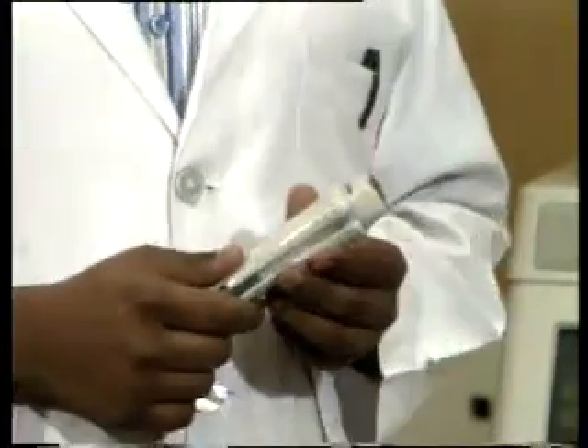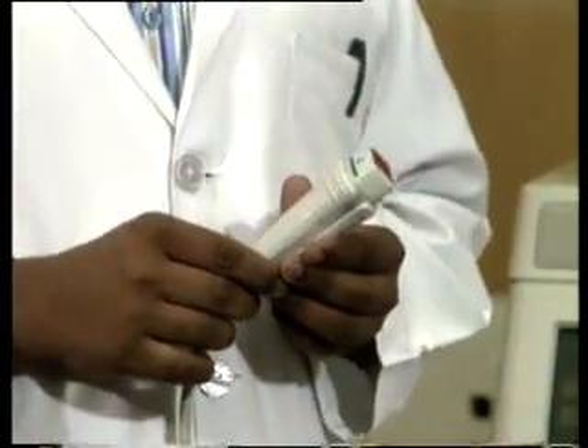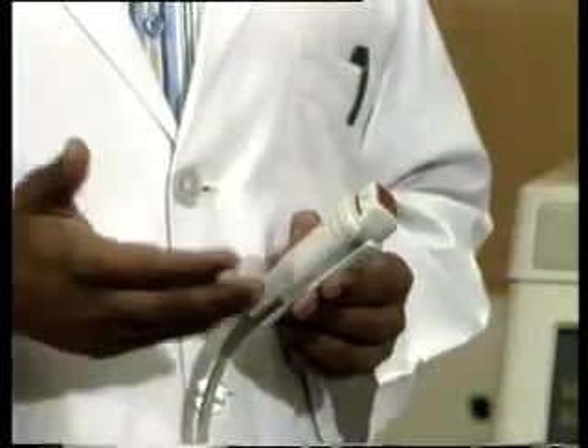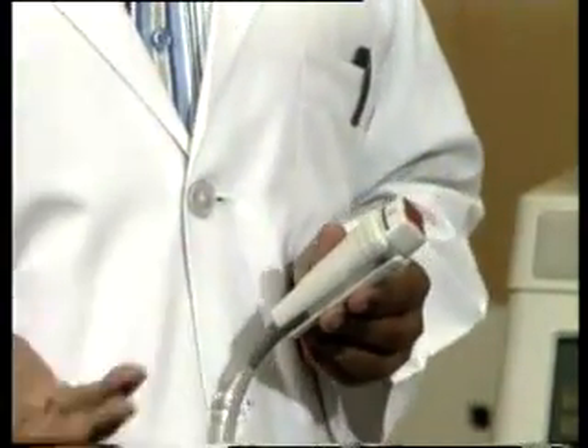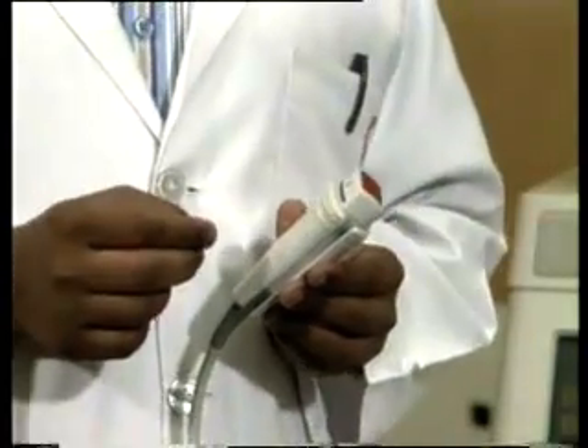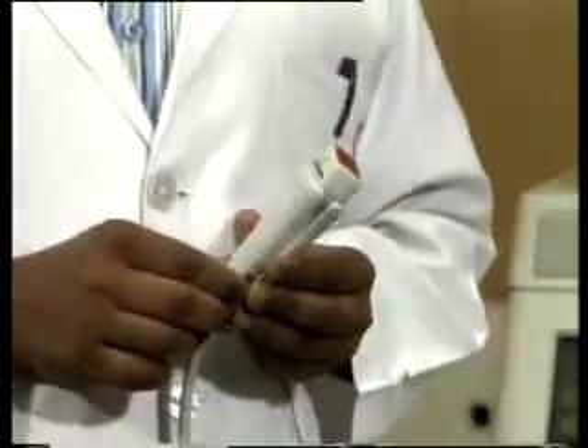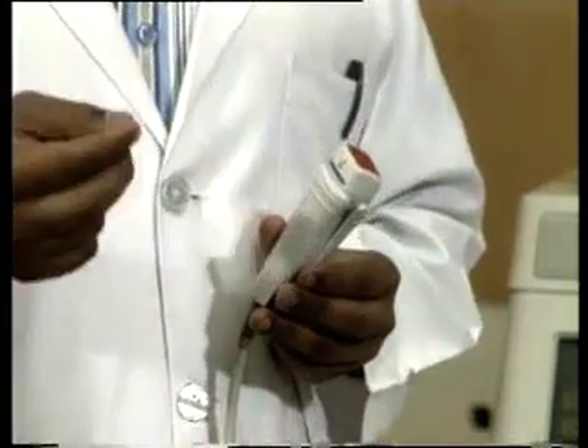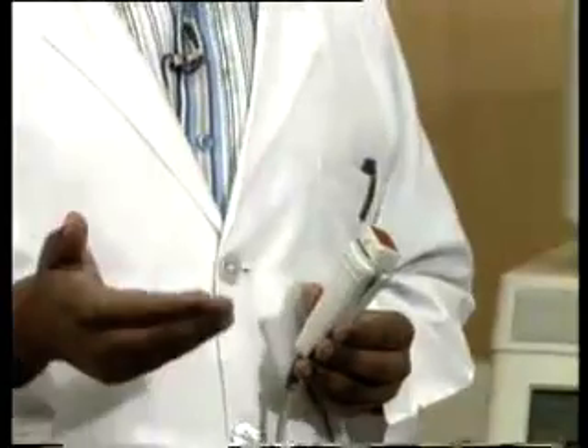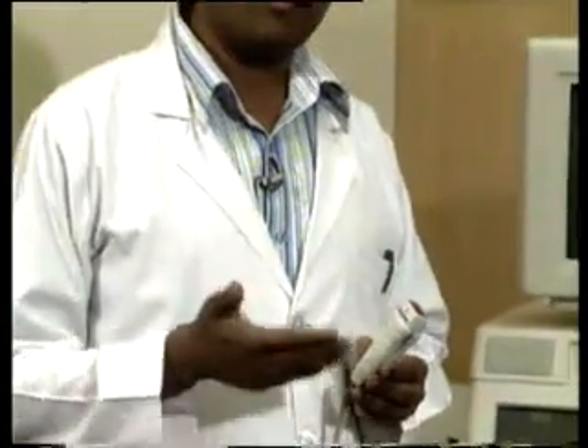So we'll first discuss a little bit about the transducer. As I mentioned, the transducer is the component which is used for transmitting and receiving ultrasound signals. The main component that transmits the ultrasound waves and then receives them back is a crystal called the piezoelectric crystal, which is present in all transducers. The special property of this crystal is that when electrical force is applied to it, it undergoes deformation, and when the force is removed, it assumes its shape again. That deformation and reformation process results in the generation of ultrasound waves, which are used for transmitting the beam into the patient's body. Similarly, when it receives an ultrasound beam, it undergoes deformation, which results in the generation of an electrical impulse that can be used as a signal. That is how a probe functions.